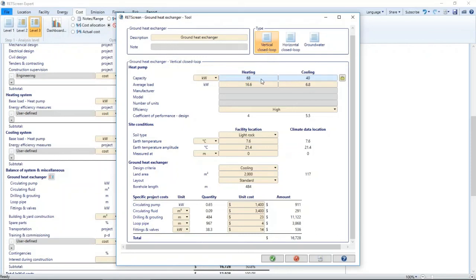The capacity was copied directly from the energy model sheet. The soil type is light rock. The climate conditions were copied from the location sheet, and the design criteria selected is cooling. The land area required for the system is calculated and must be compared with the land area available. The model calculates the ground heat exchanger pump size, quantity of circulating fluid, and pipe size. The various costs are also calculated.